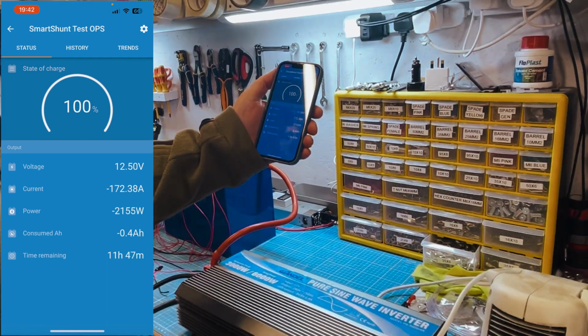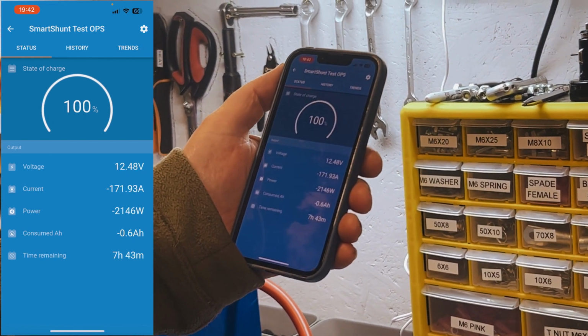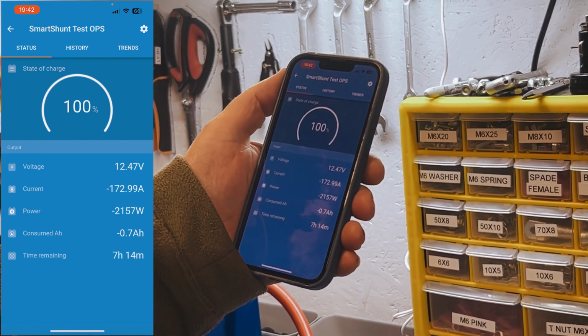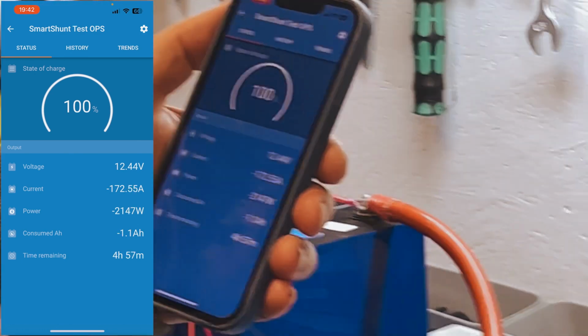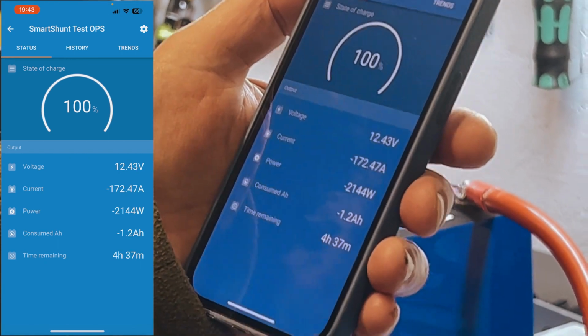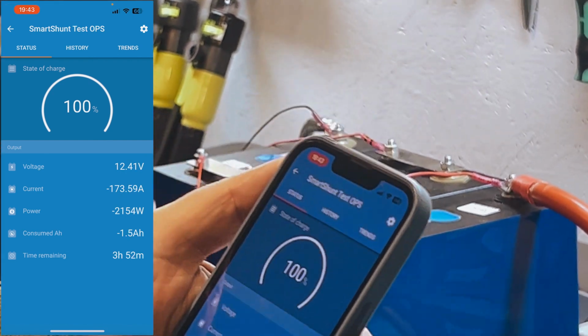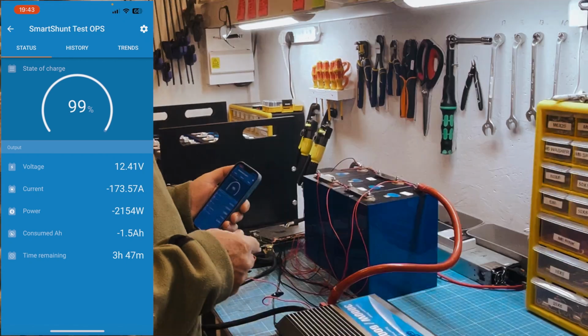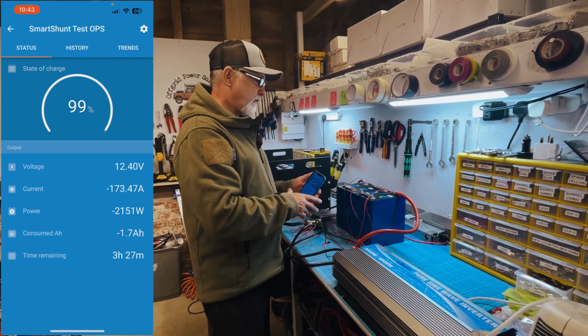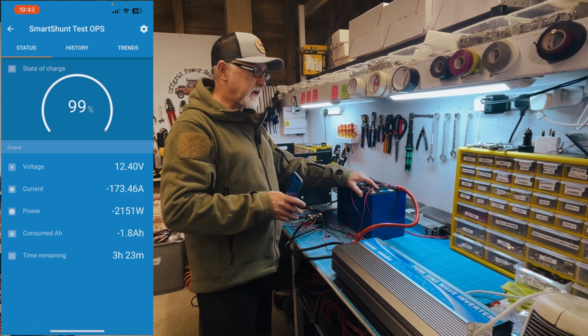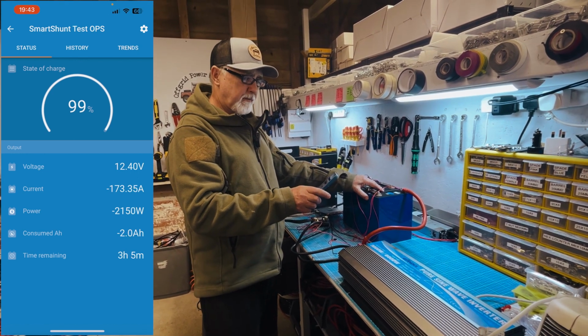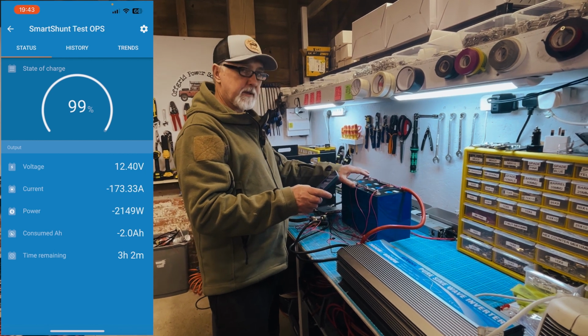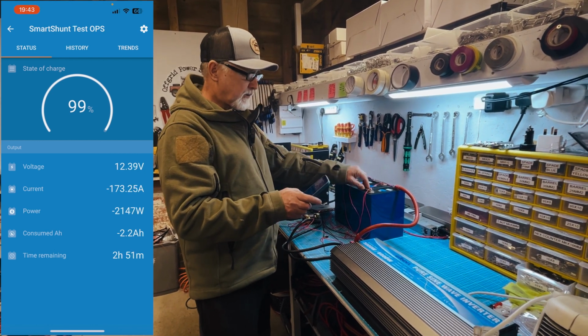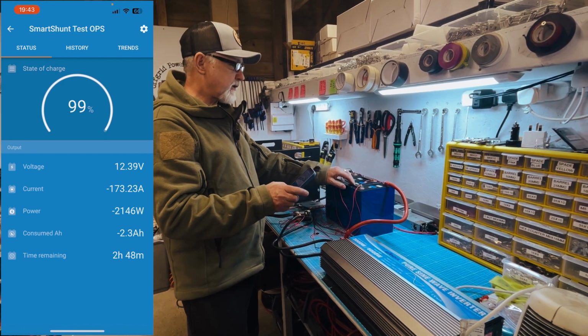Running at 172 point something amps, 171, 172 amps, so quite a high current draw. This is going to flatten this battery. It's a 280 amp hour battery, so just over an hour and 20 minutes or so, and this battery should be completely flat, and then we will know what the capacity is. The idea is we want to test the capacity of these cells under a very high current draw - 170 something amps, which is a pretty high current to be going through these. These are quite small bus bars, so I'll be interested to see how much they heat up.